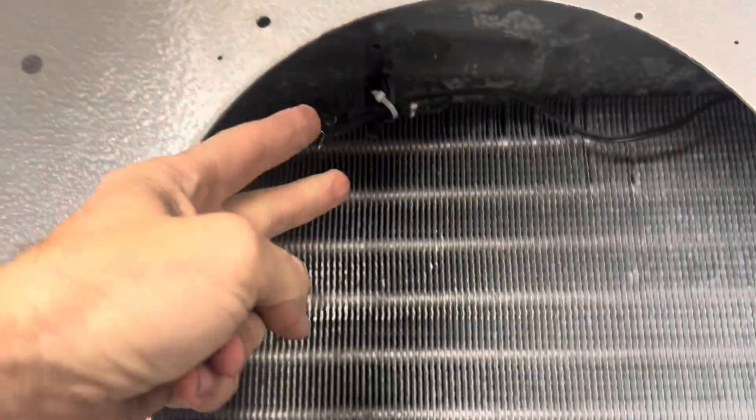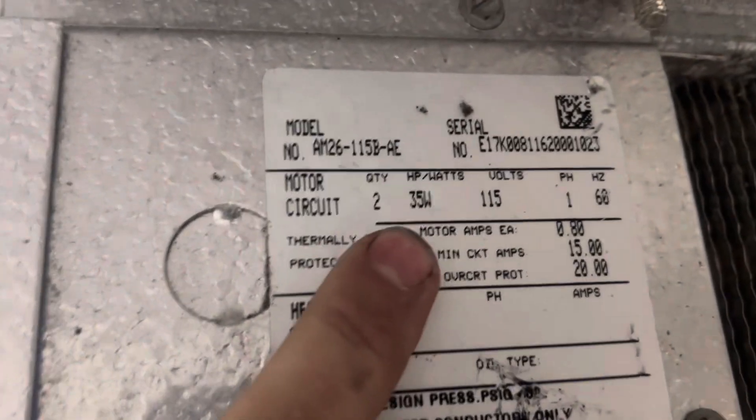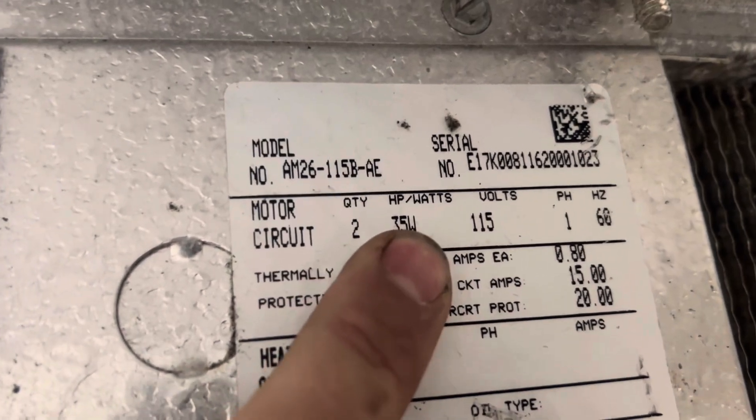We disconnected our fan and connected our meter leads to that. We set our meter on voltage, and then we looked at the tag and said we have two 35-watt fans, 115 volts. Fire it up. And when we fired it up, we had 120 volts at our meter. So we knew that was what it was going to be.